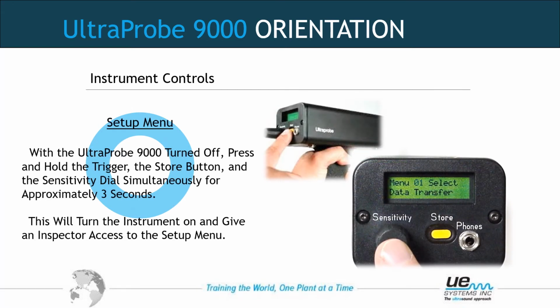The setup menu. So as far as the operation, we just went through that. The setup menu is easily achieved by letting the power go off, then pressing the sensitivity and storage button at the same time, as well as pulling the trigger. All three must be done at the same time. Typically, you can push the sensitivity and storage button in by themselves, then pull the trigger and hold all three until you see this. Menu 1, select data transfer. This is how you upload and download a route to the computer to the DMS software.